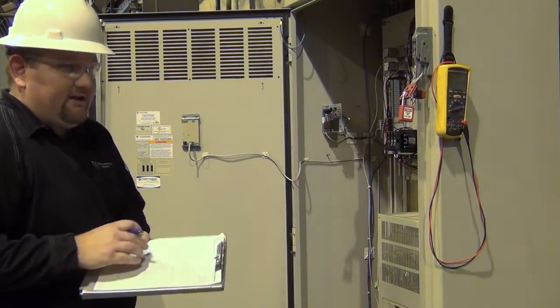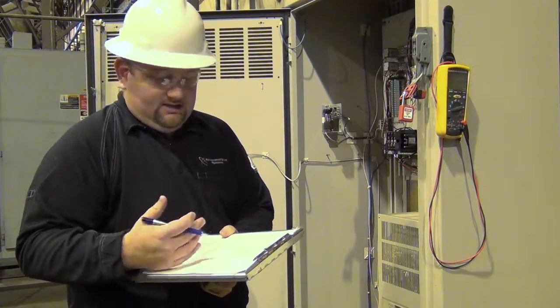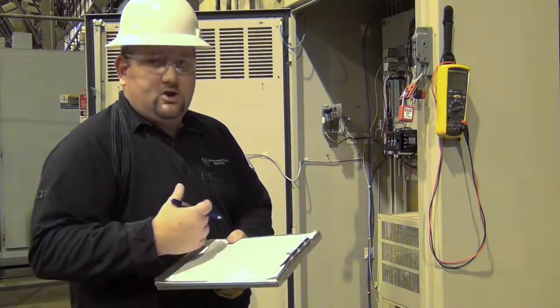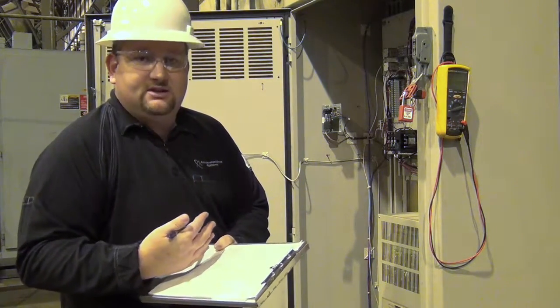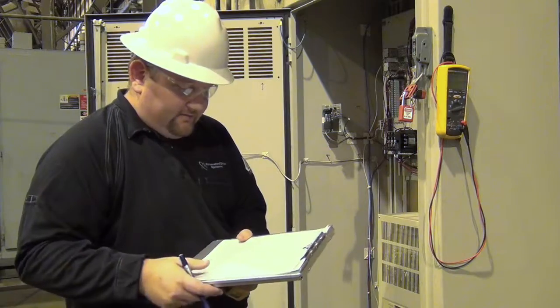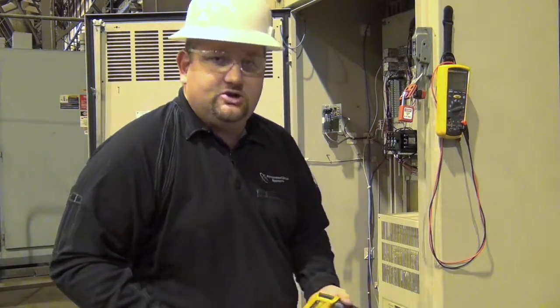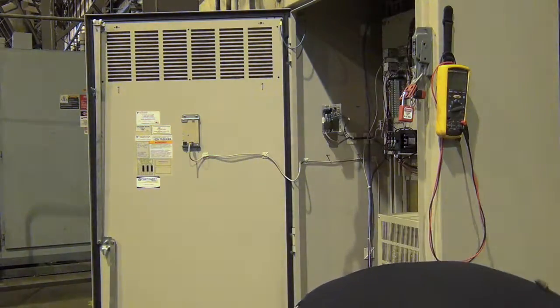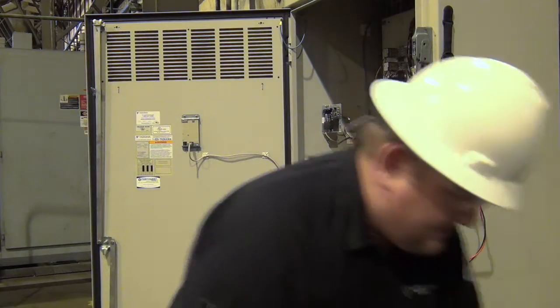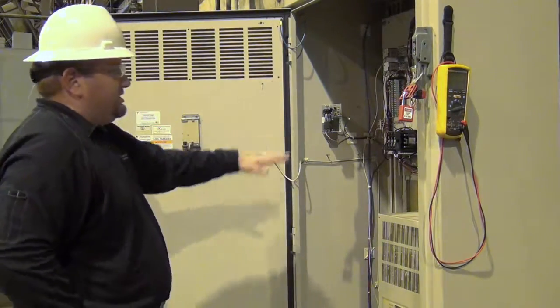So since this drive wasn't running, ordinarily if you come to a drive that was in service, at this point you would record the heatsink temperature and record the volts and the amps that the drive was running at when you arrived. So the next thing we're going to do is go through and check all of the wiring connections inside the drive. So we're going to start by checking all of the control circuits.